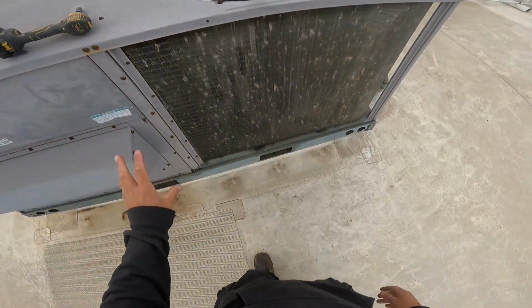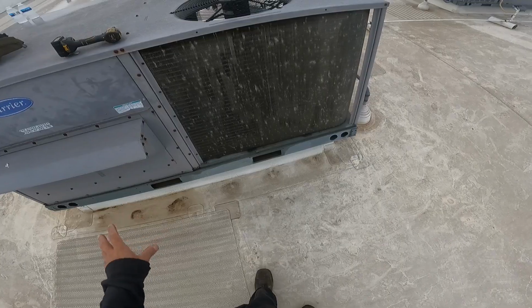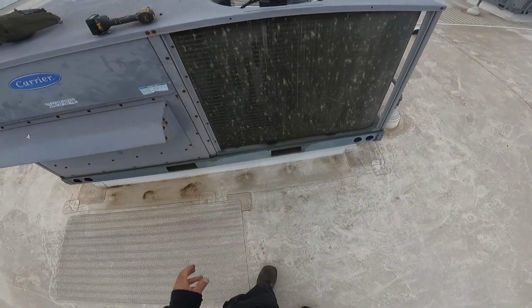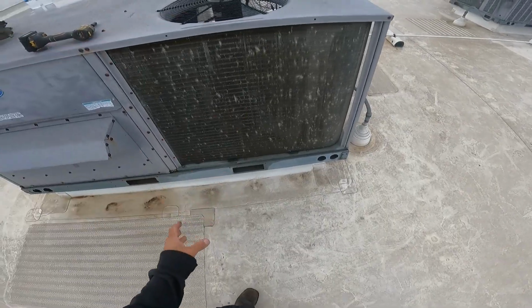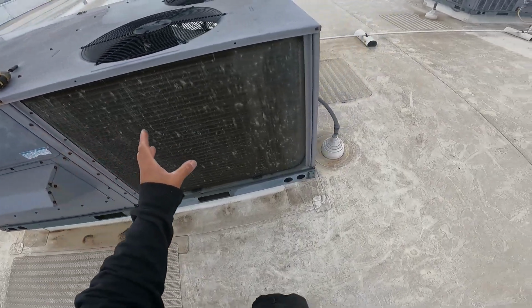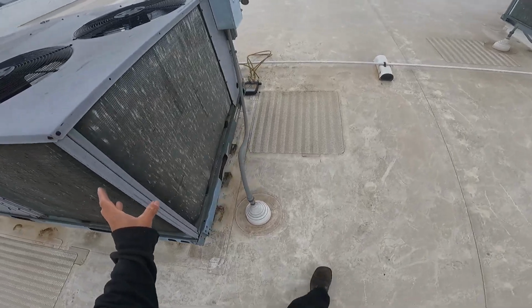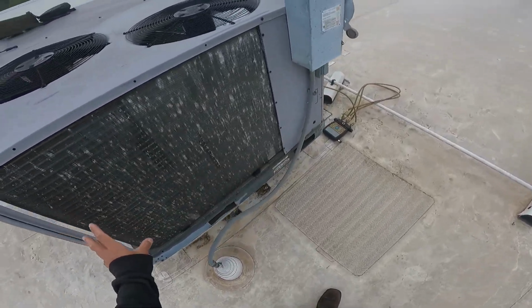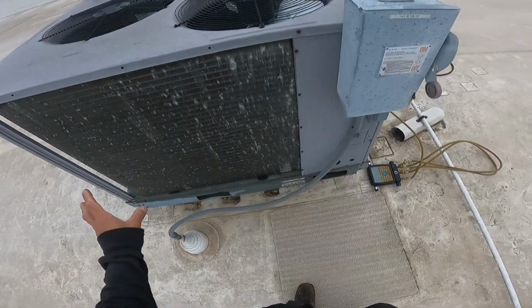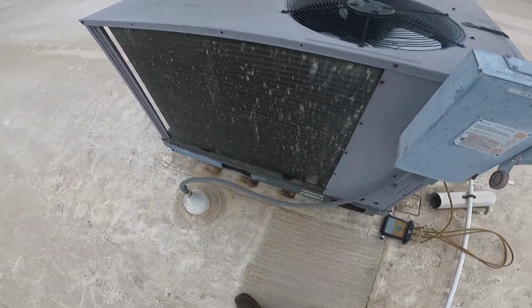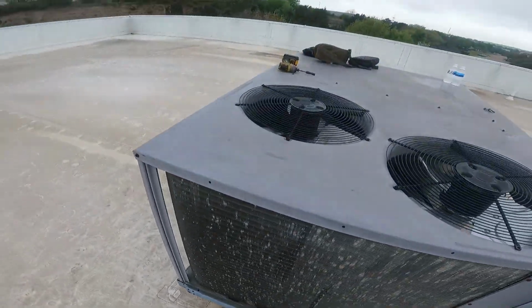We'll glance around the condenser coil here. There's light hail damage - nothing I'm concerned about, nothing I'm going to write up. I'm going to look up and down this coil. If there's a leak on the coil, you're going to see a big wet spot. I don't care if it's just rained or not - oil and water don't mix, so the oil will still be present on whatever part of the coil is leaking. I don't see anything leaking here.